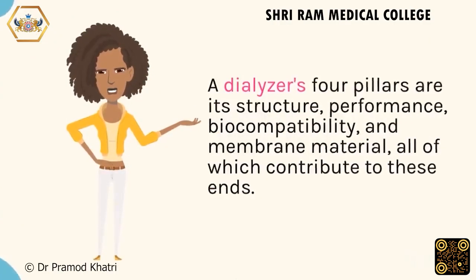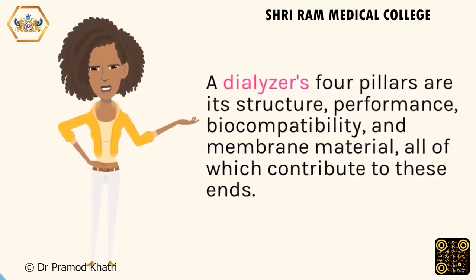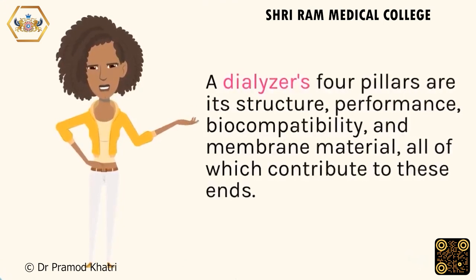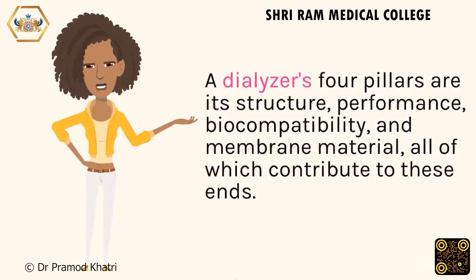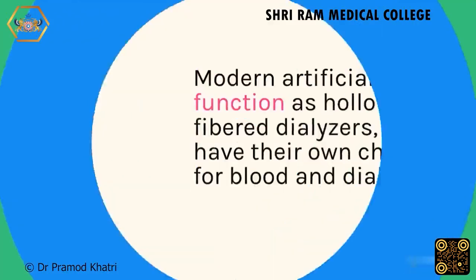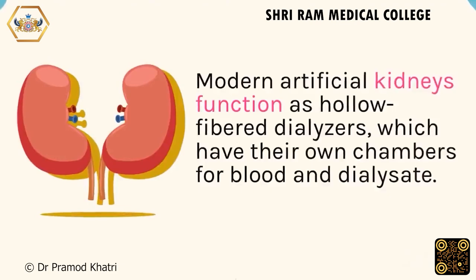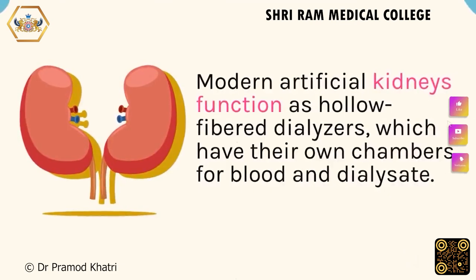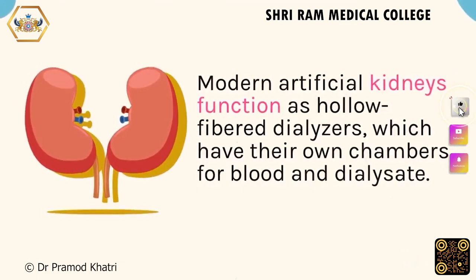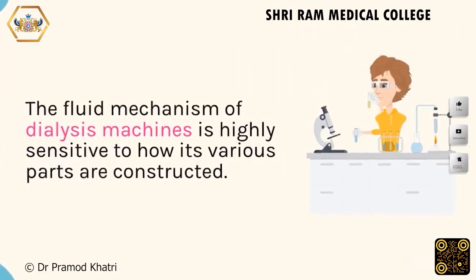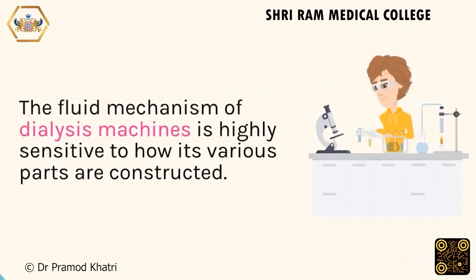A dialyzer's four pillars are its structure, performance, biocompatibility, and membrane material, all of which contribute to these ends. Modern artificial kidneys function as hollow-fibered dialyzers, which have their own chambers for blood and dialysate. The fluid mechanism of dialysis machines is highly sensitive to how its various parts are constructed.